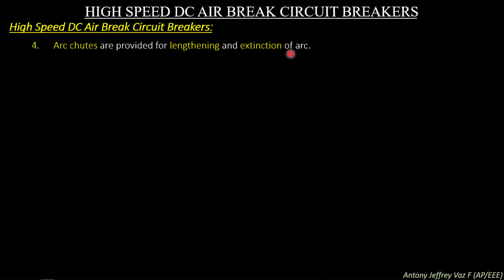Arc chutes are provided for lengthening and extinction of the arc. So in a DC circuit breaker, arc chutes will be provided to lengthen and extinguish the arc. The contact is held closed against the action of the opening spring by an armature attracted to a shunt excited electromagnet. So the opening spring will be connected with the armature, and when the armature is released, the spring lever will trip and the whole circuit breaker will trip the circuit.